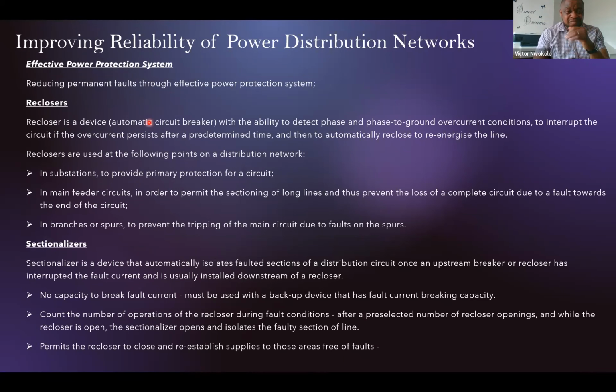Improving reliability further. I'm looking at how effective protection helps there. One thing we'll aim to do is to reduce permanent faults through a proper protection system. And this is done by the use of two very common equipment in the advanced world. In Nigeria, this is not very popular, but if these two equipments are introduced into the Nigerian distribution system, that would help a lot. And one of them is the recloser. Recloser is a type of automatic circuit breaker. It's designed and placed at intervals on the overhead distribution network.